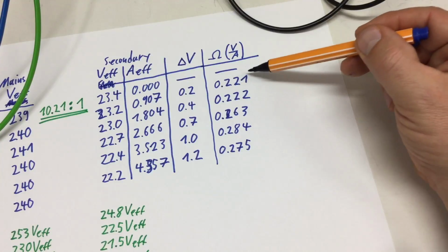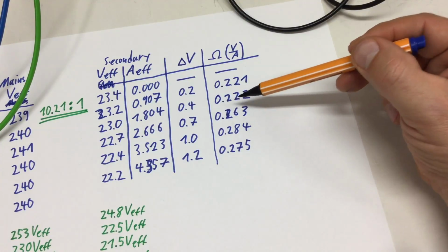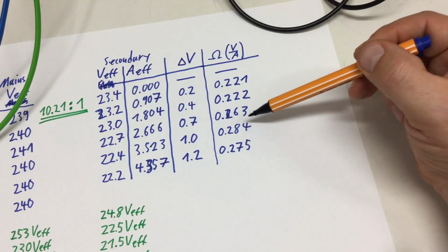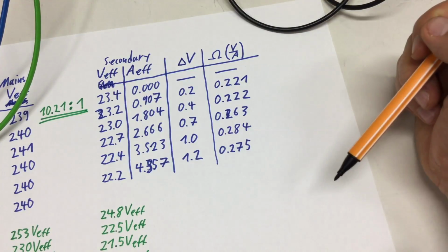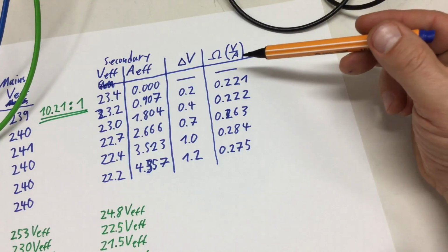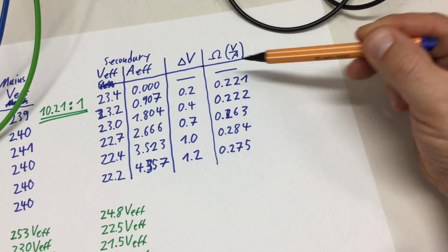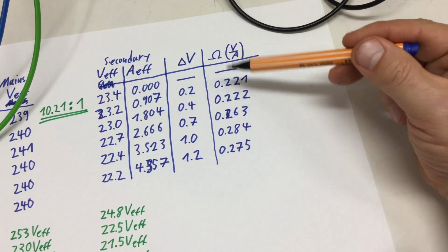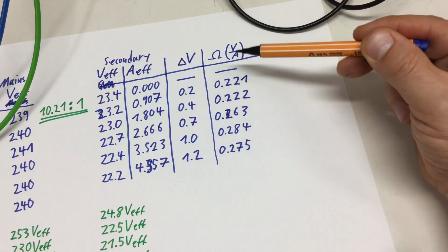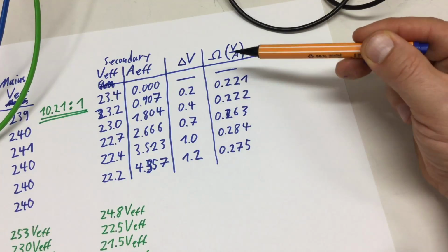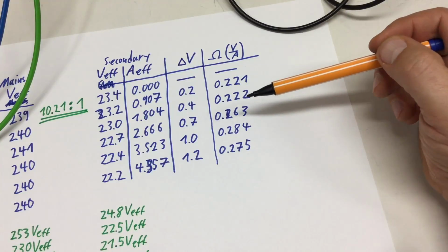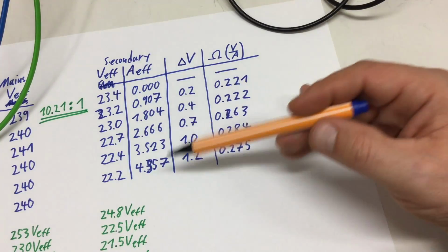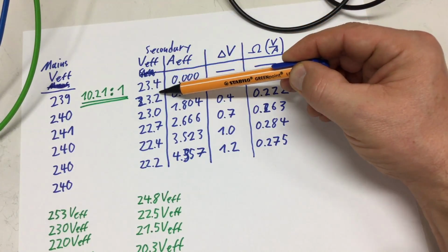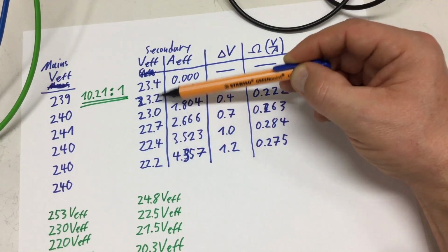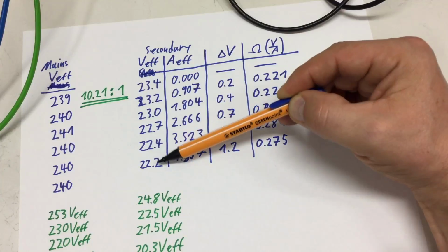And we get these resistance values: 0.221, 0.222, 0.263, 0.284, 0.275. And that spread should not be there. So maybe I'm not measuring wrong, but I mean, we're measuring here the voltage on the last digit, which is always a bad idea on digital instruments, measuring something on the last digit.